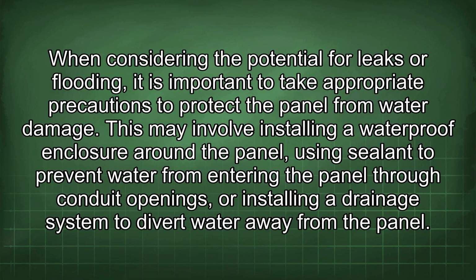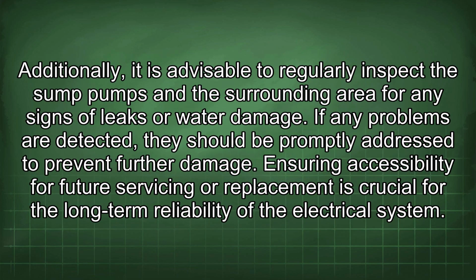When considering the potential for leaks or flooding, it is important to take appropriate precautions to protect the panel from water damage. This may involve installing a waterproof enclosure around the panel, using sealant to prevent water from entering the panel through conduit openings, or installing a drainage system to divert water away from the panel. Additionally, it is advisable to regularly inspect the sump pumps and the surrounding area for any signs of leaks or water damage. If any problems are detected, they should be promptly addressed to prevent further damage.